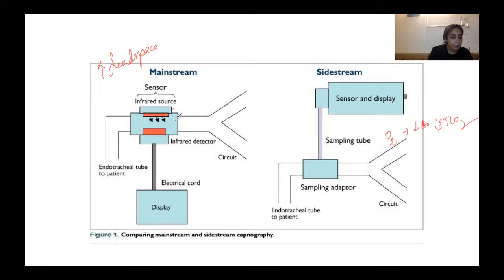All right. With the side stream, the accuracy actually decreases with an increasing respiratory rate, and the sampling is no longer effective. Basically, the sampling flow rate should be proportional to the size of the patient for the side stream.